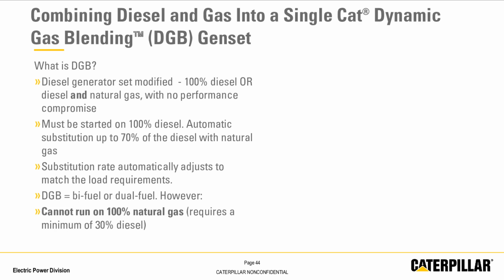I would also note that DGB is sometimes referred to as bi-fuel or dual fuel. Those are terms that are commonly used, but it's very important to note, it cannot run on 100% natural gas. It always requires a minimum of 30% diesel. So though it's sometimes called dual fuel, it's either all diesel or a mix of both diesel and gas, but never gas alone.